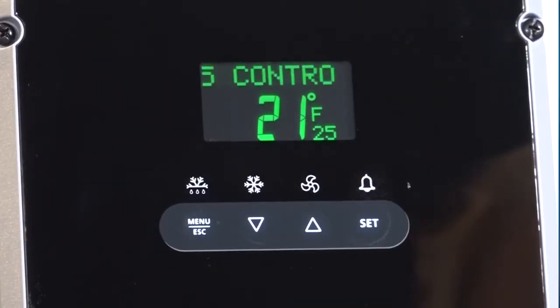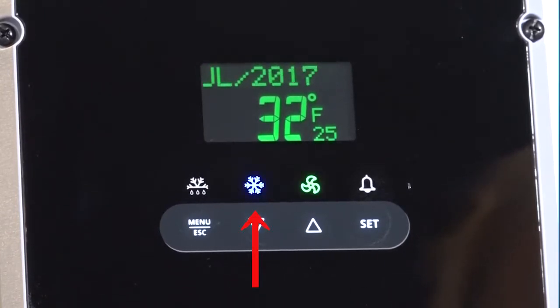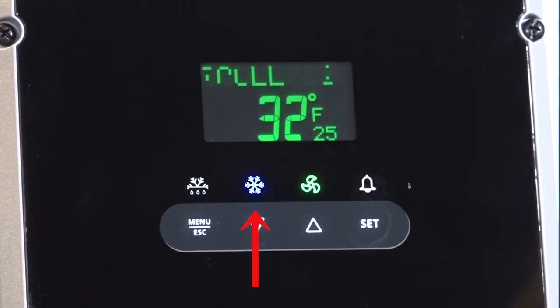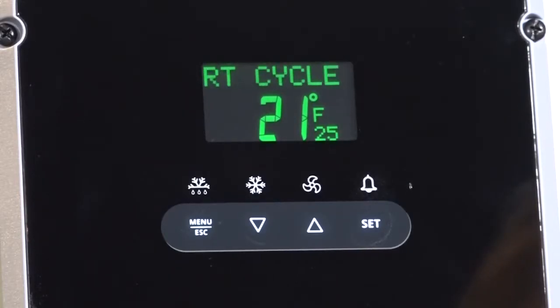The snowflake icon represents the refrigeration cycle. The icon will be illuminated when the compressor is running. There's also a possibility that there could be a call for cooling, but the icon is not illuminated. This could be an anti-short cycle timer or delay after defrost cycle. This can be noticed on the main screen. Again, the main display will indicate the cause for the delay.